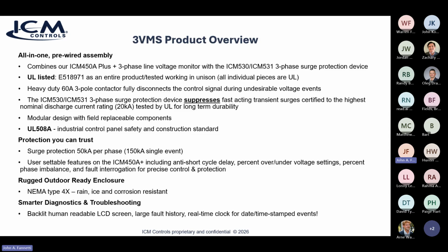The 450A Plus is fantastic at three-phase voltage monitoring. Again, why do you need a voltage monitor? Because you get phase loss, phase unbalance, and phase reversal with three-phase. You've got to be able to pick that up, as well as the top of the line three-phase surge suppression we offer, the 530 and the 531. Those are for clamping those transient surges that a voltage monitor can't catch. A voltage monitor can't catch a surge. It can take care of phase loss, phase reversal, phase unbalance, great, but it cannot catch a surge. So that's what you need, the surge suppression.